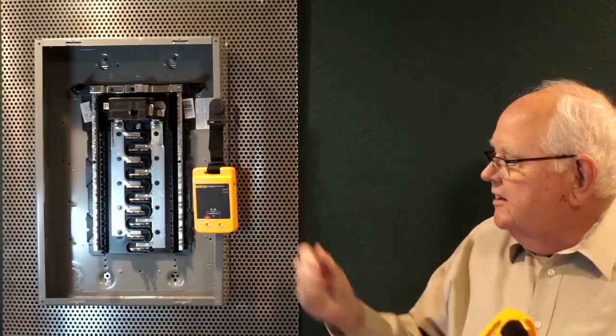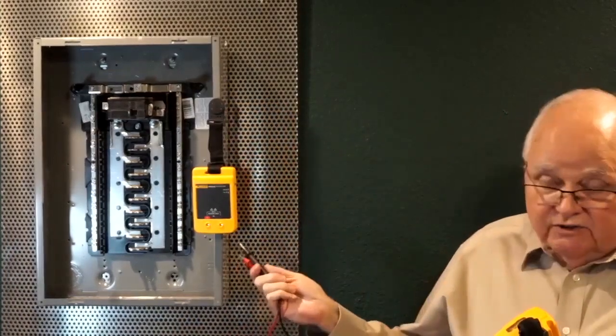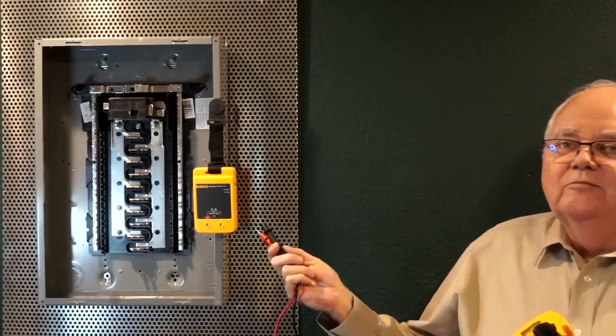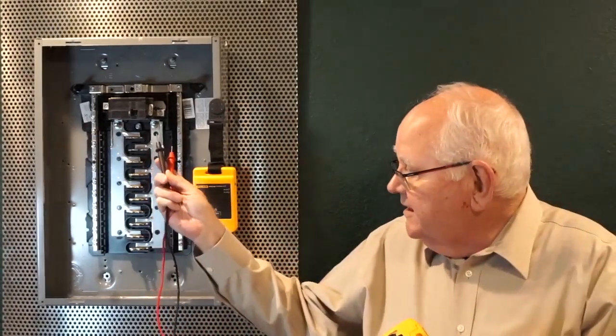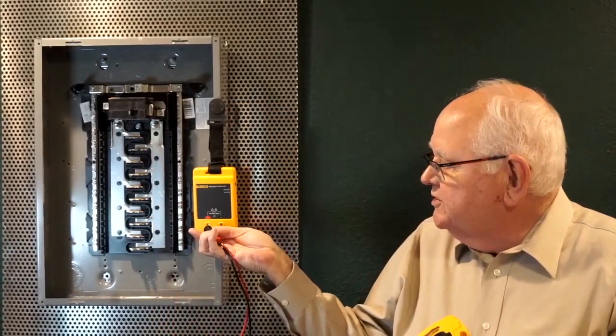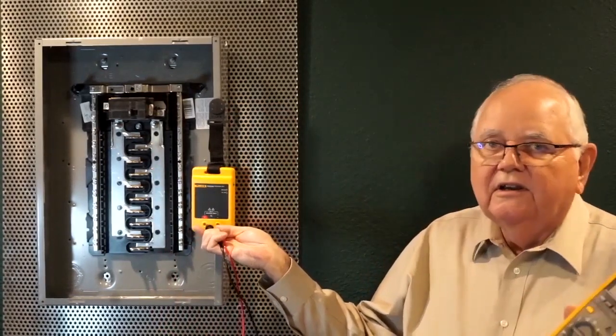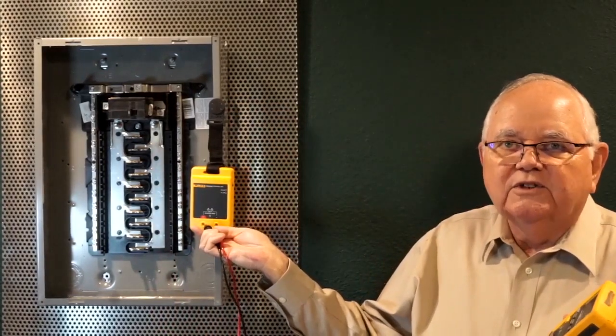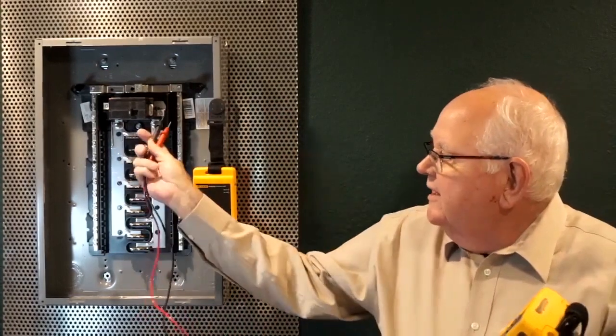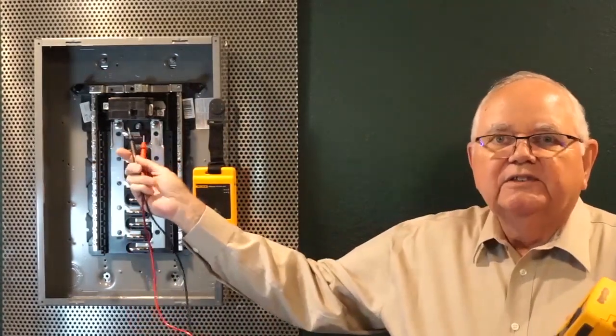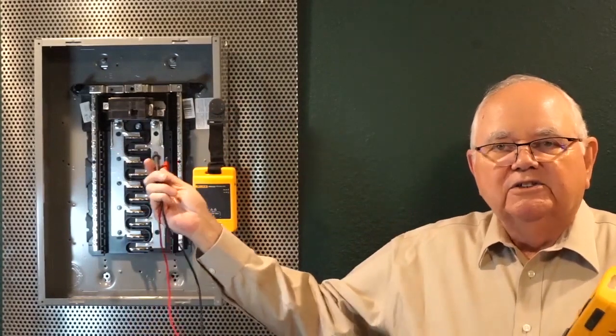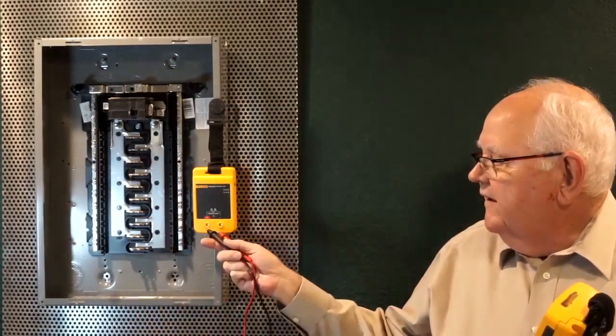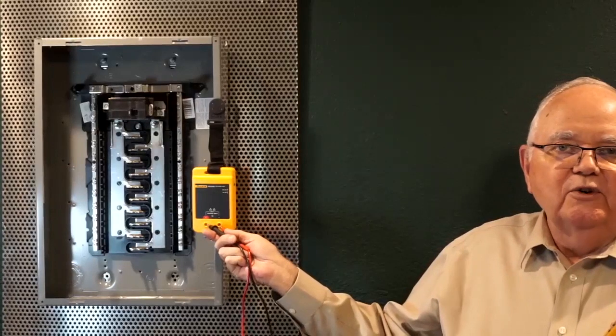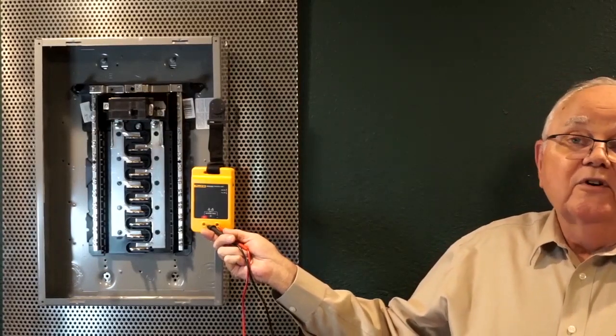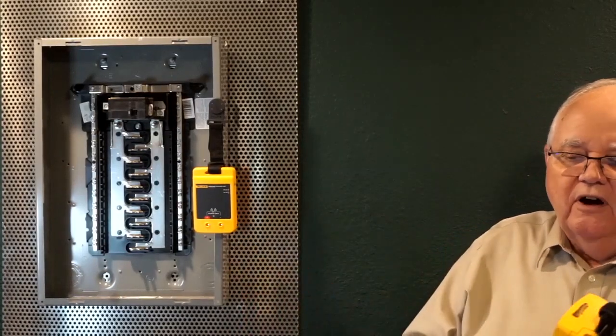I can put my proving unit very close to the equipment that I'm working on, which is an advantage. And then I push those little two buttons in and my meter would read 240 volts, letting me know that it works on voltage. Then I come over here and check once again from phase to phase and phase to ground, make sure that I get 0 voltage, and then come back and make sure that my meter still works properly. 3-point method, or live dead live test, we often call it.